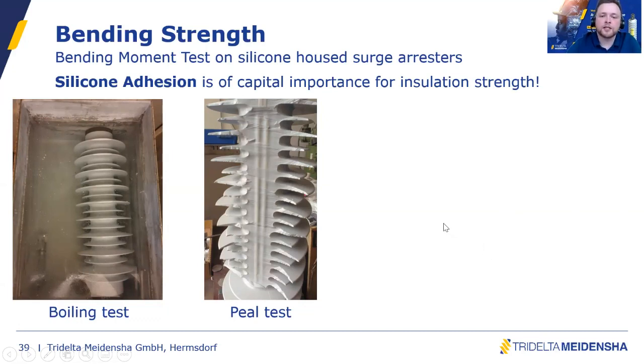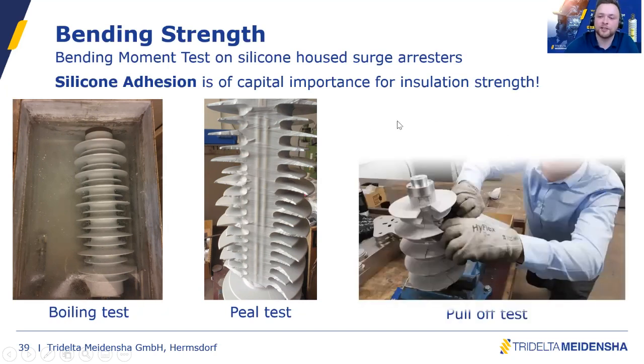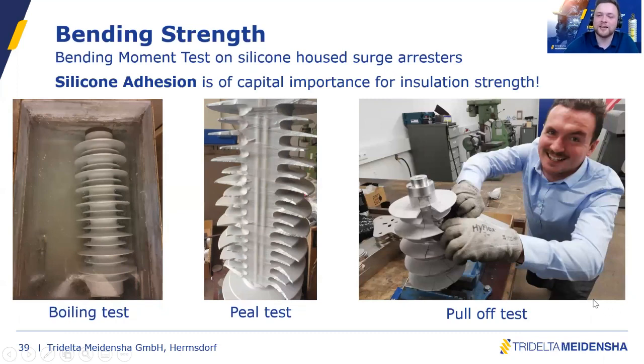And another test is the pull-off test, and therefore I had a little competition with my colleague Florent, and he made a bet that he could take a random silicone housed surge arrestor out of the production, and he could easily pull off the silicone to show me that our bending strength, our silicone adhesion is not good, and I accepted the bet. So he took a random surge arrestor from our production and he tried to make the pull-off test, and here in this wonderful picture you can see the pain in his face as he struggled to get off the silicone. So what I want to tell you with that is that we are taking special care for the silicone adhesion, and we are testing it regularly, and this is a very basic feature of the Tridelta surge arrestors, that they provide a very good silicone adhesion.